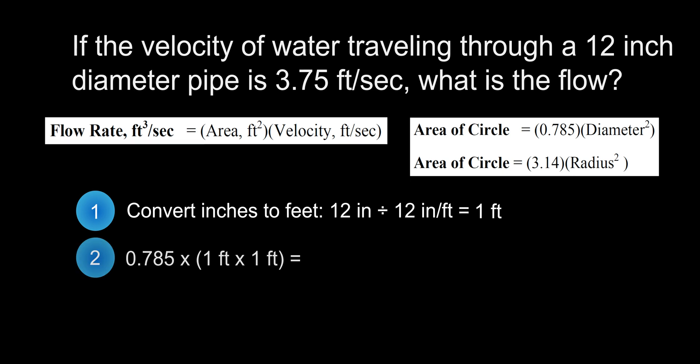In step 2, we will use the area of a circle formula. I have opted to use the version with diameter squared because the question uses diameter already. This will look like 0.785 times 1 foot squared. This will solve for the cross-section area of the pipe, which in our case equals 0.785 square feet.